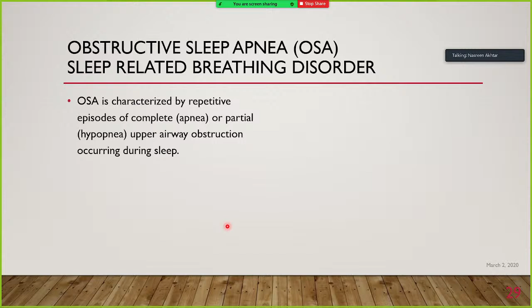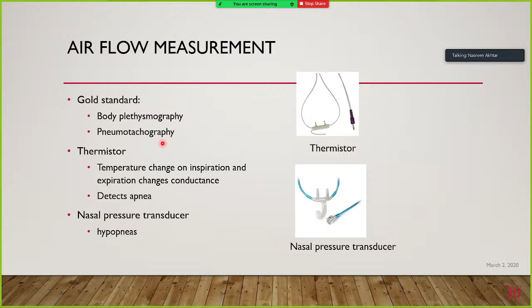Airflow measurement is done with the use of these electrodes. This is a thermistor. So there are these two metal wires that you see over here and one at this end. Their basic principle is that they detect the temperature change on inspiration and expiration. This changes the conductance of the metal, and this shows us the flow. This one is the nasal pressure transducer, in which there is a change in the pressure of the airways. There is a pressure transducer at the end of this, which will detect the pressure changes. And the use of these two is that the thermistor is more accurate in detecting apneas, that is complete cessation of breathing, and the pressure transducer is better for detecting the hypopneas, that is there is a partial reduction of breathing during this time. The gold standard is body plethysmography and pneumotachography, but it is not done in polysomnography.